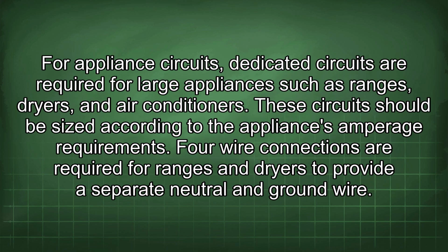For appliance circuits, dedicated circuits are required for large appliances such as ranges, dryers, and air conditioners. These circuits should be sized according to the appliance's amperage requirements. 4-wire connections are required for ranges and dryers to provide a separate neutral and ground wire.